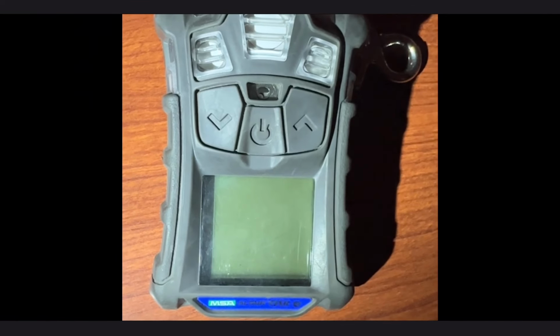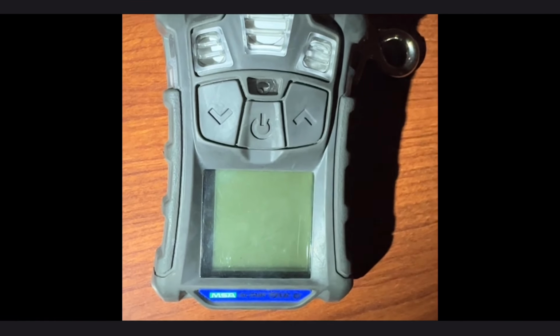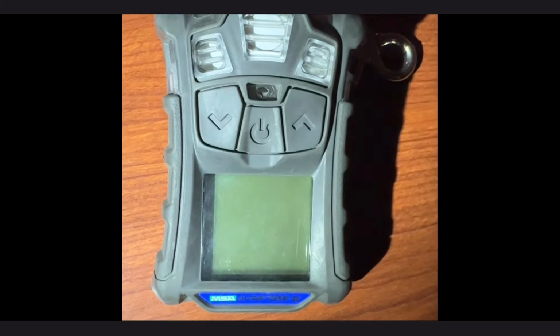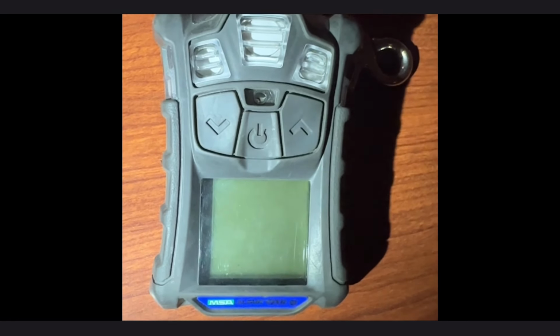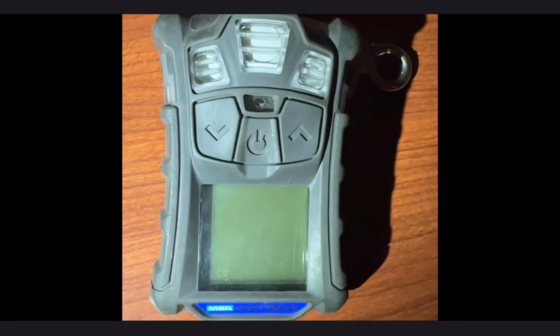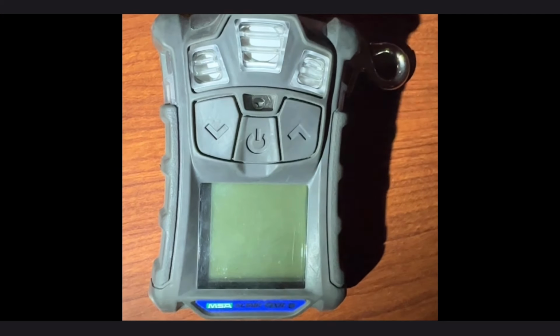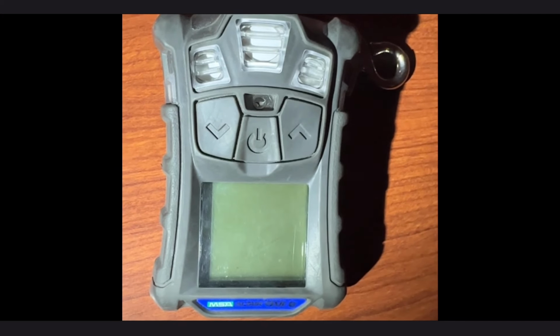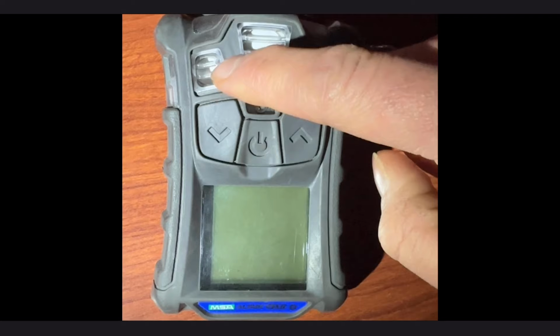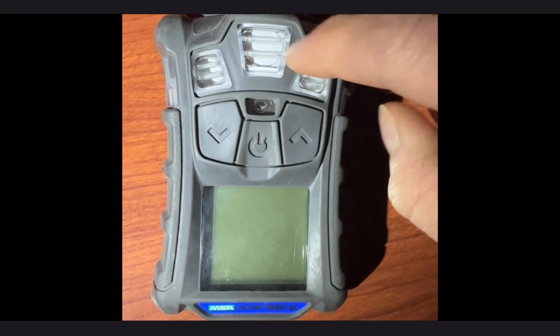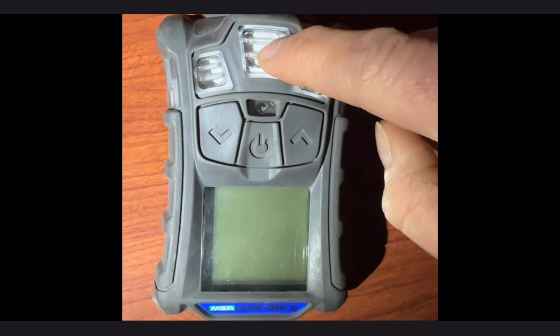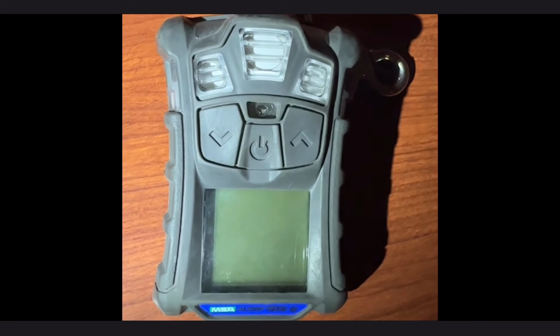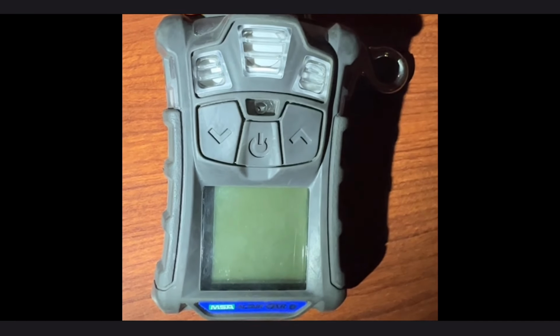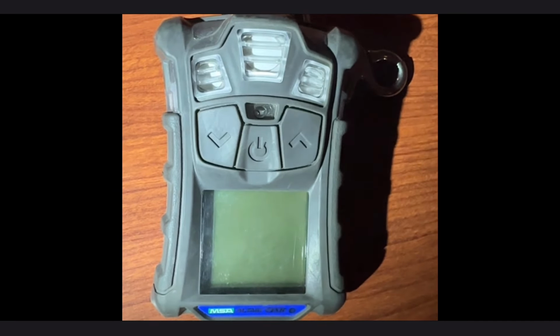All right, as promised, we're gonna go over the new MSA 5X gas monitors, and I'm gonna compare them with the old ones, the Altair 4XRs. They're both MSA products, same sensors as before. We have 3 sensors. In the old style, the sensors are right here. One's a combination sensor for toxic gases. So we actually monitor 4 different things, which we'll go over, but there's only 3 sensors because one does 2.